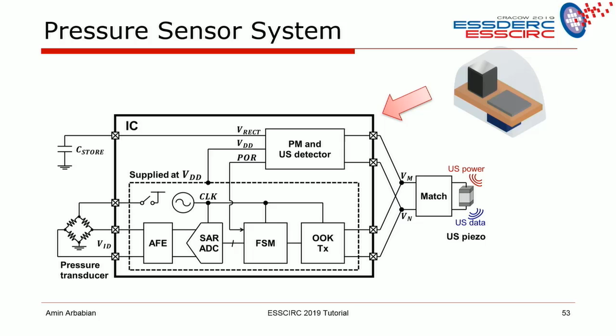So from a timing perspective, if you look at this on the bottom left, we start from an ultrasound power coming in. Then we have a quiet period, a wait period. We want all the ultrasound to die down. Remember, ultrasound is a pressure wave, and here we're measuring pressure. So you don't want to have a pressure wave as you're measuring pressure, because there's always going to be some harmonic, imagine sort of an IM2 effect that changes your DC pressure. So we have a wait period after the ultrasound power to let all the echoes dissipate.